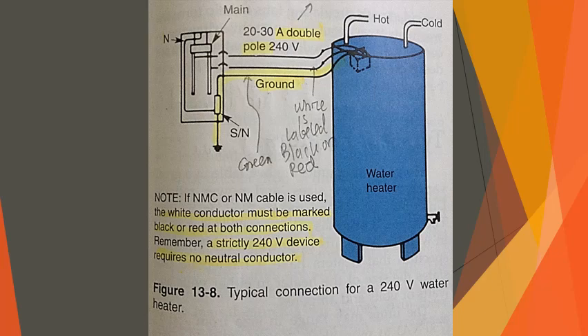Water heaters, like most electrical equipment, must be properly grounded. This is accomplished by bonding the water heater unit casing to the equipment grounding conductor of the cable, or to the conduit, if supplied in that manner. Additional bonding to the metal cold water supply pipe is recommended.